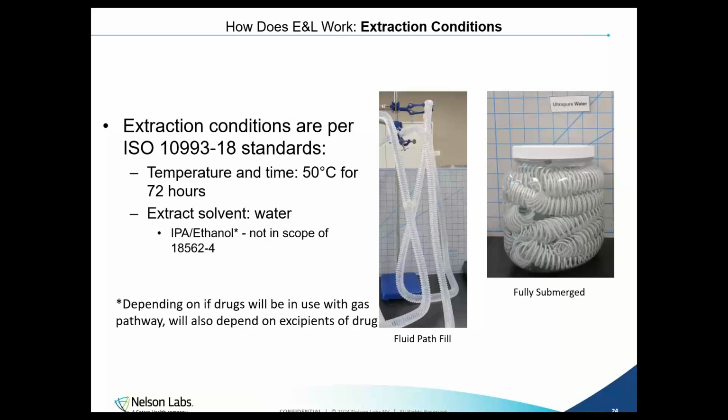However, when the device is submerged, we will get an assumed exaggerated amount of extractables detected due to both the gas pathway and the external surfaces of the device being extracted. Because of this, it is a more worst-case extractables profile. However, these results may also be able to be scaled accordingly. For example, if the internal and external surface areas are exactly the same, and they make up 50-50 of the device, the results seen may be scaled by half.